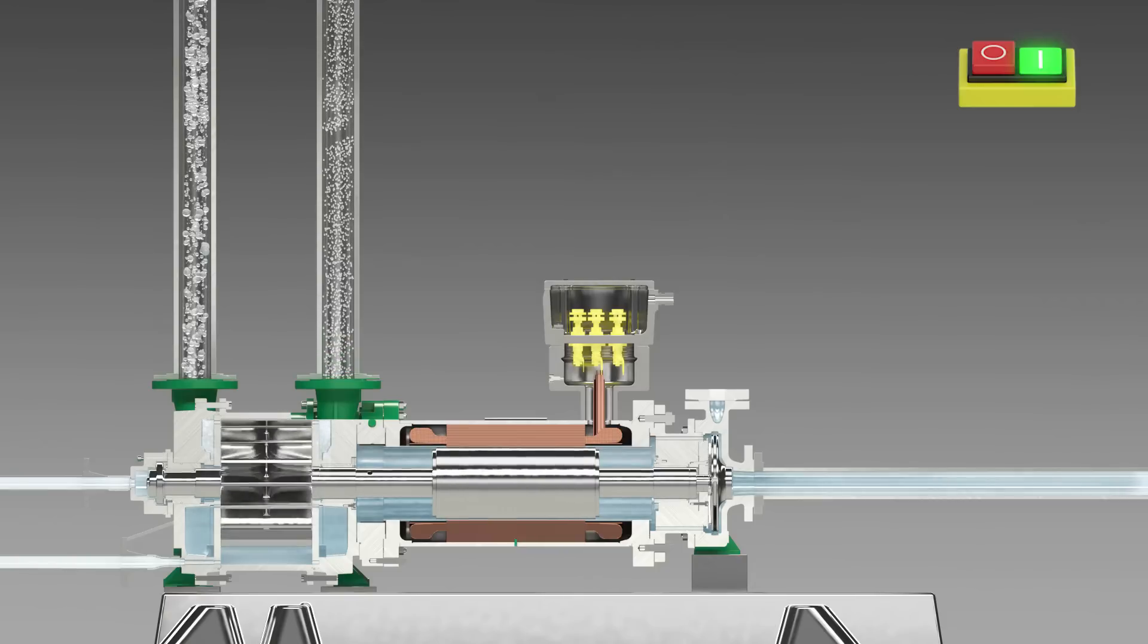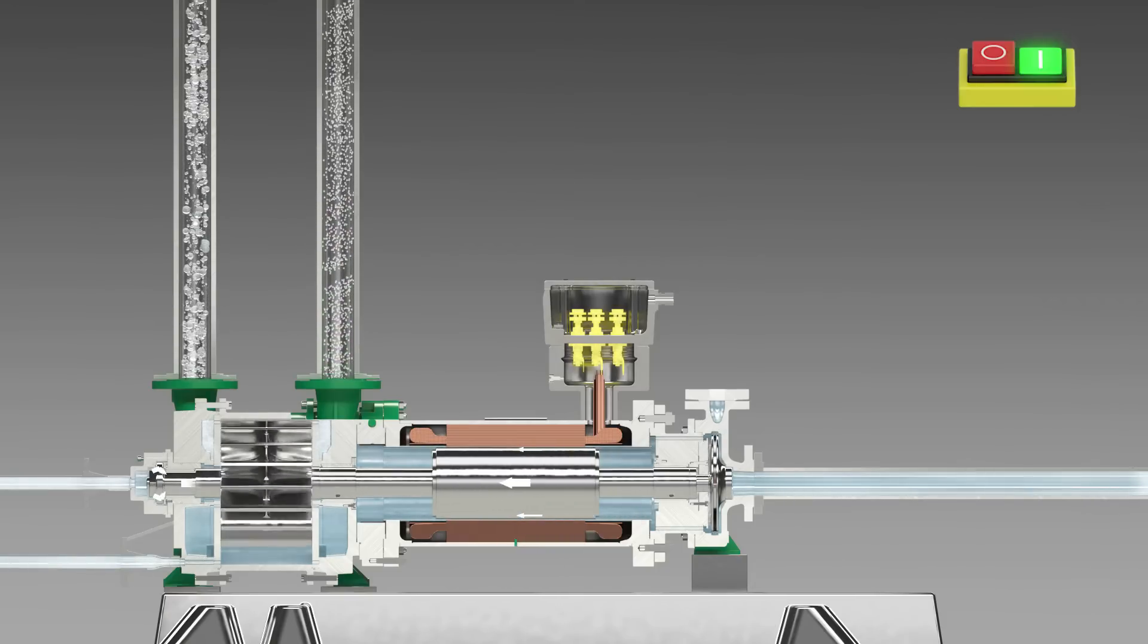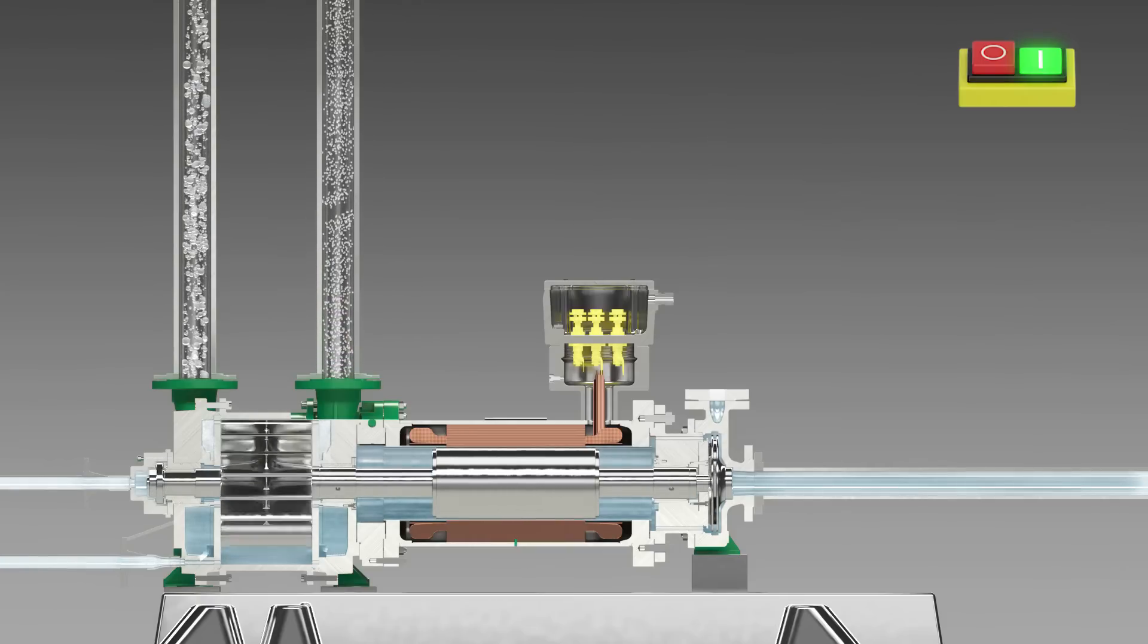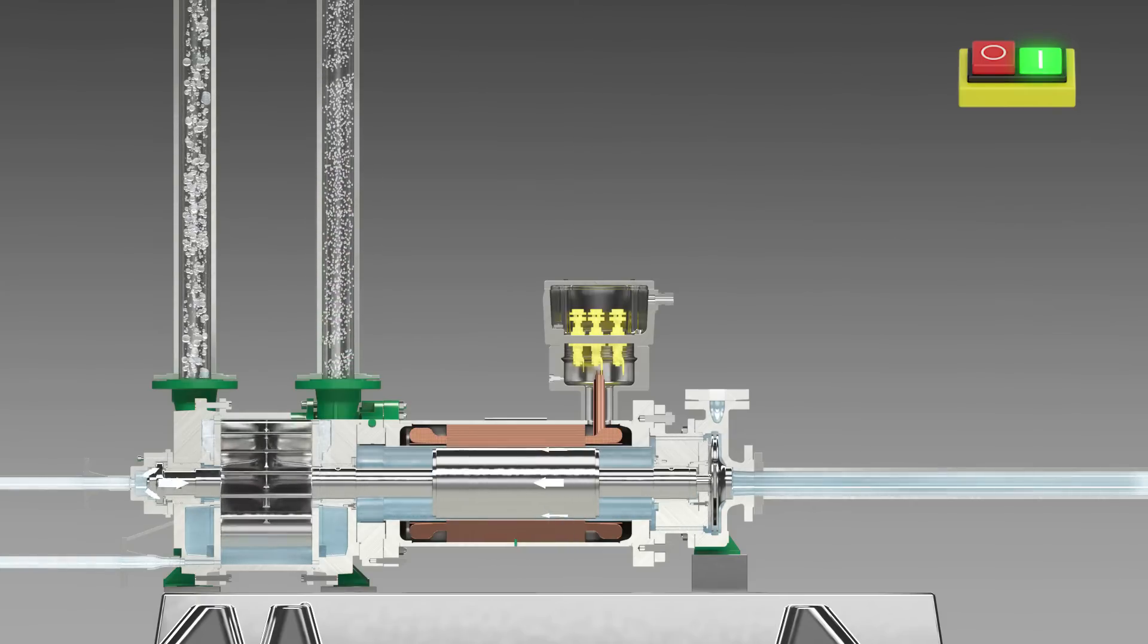To cool the motor and lubricate the hydrodynamic plain bearings, the operating fluid is fed in separately on the motor side and returned to the pumping chamber using the rotor with the help of an internal impeller.